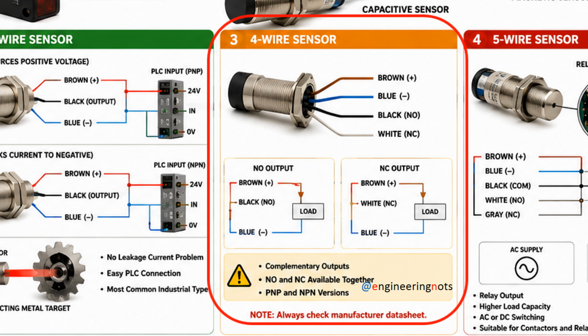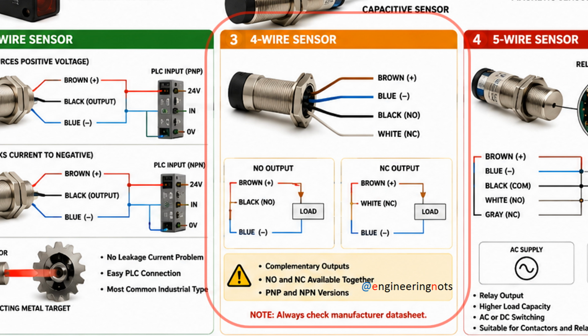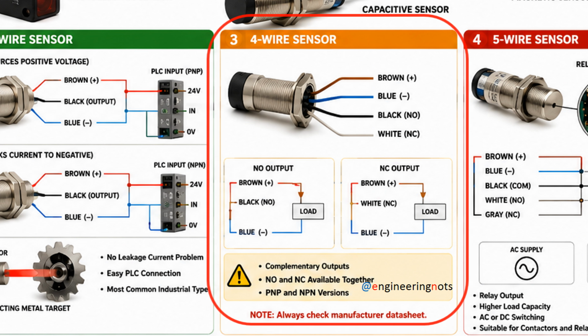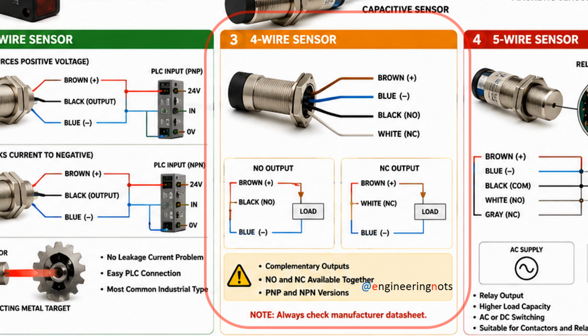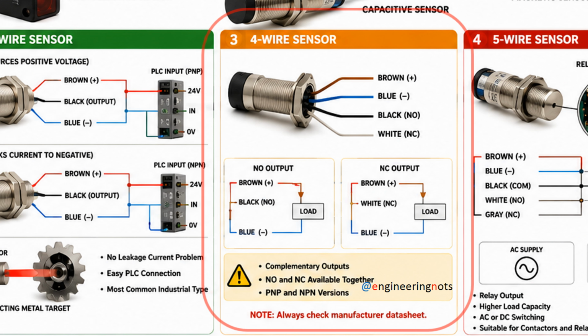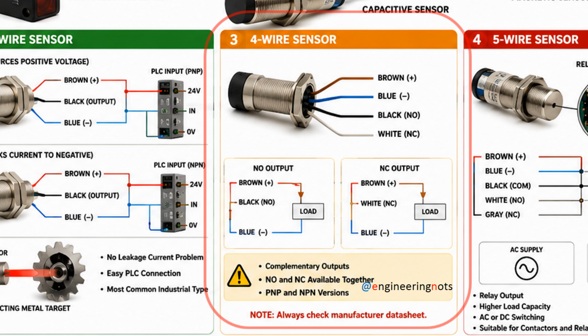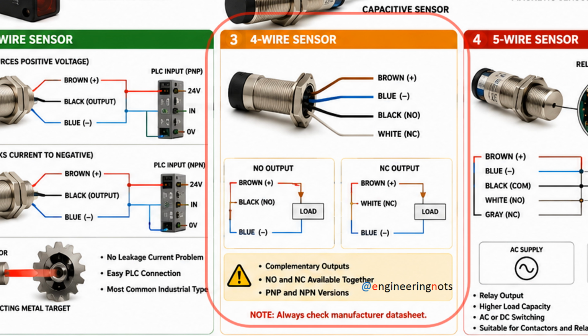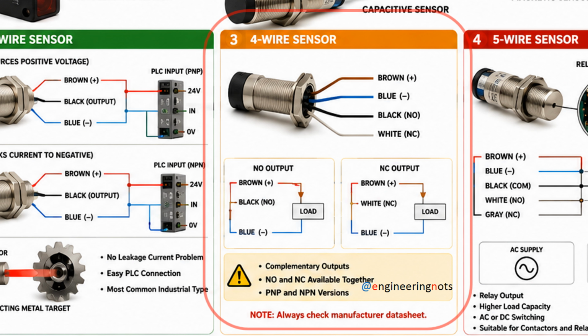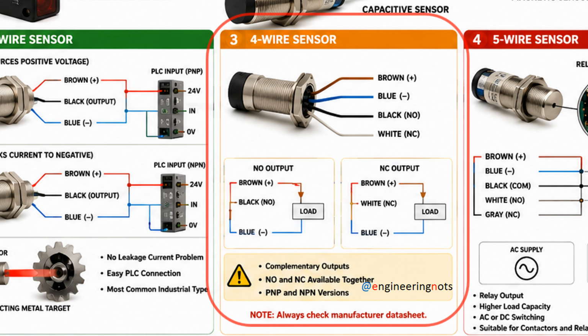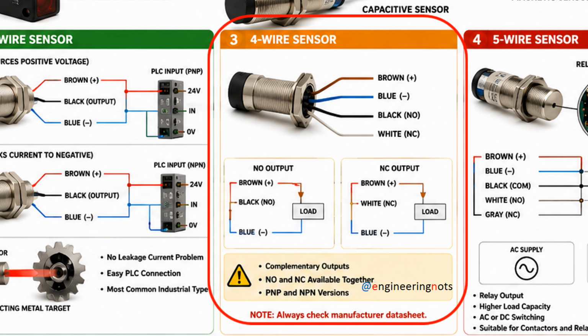Now we move to 4-wire sensors. Up to this point, every sensor had only one output. However, in some applications, we need both NO and NC outputs at the same time. What is NO? NO stands for normally open. In its normal state, the output is open. When the sensor is activated, the output closes. What is NC? NC stands for normally closed. In its normal state, the output is closed. When the sensor is activated, the output opens. The biggest advantage of a 4-wire sensor is that both outputs are available simultaneously. As a result, a single sensor can be used for multiple control circuits.